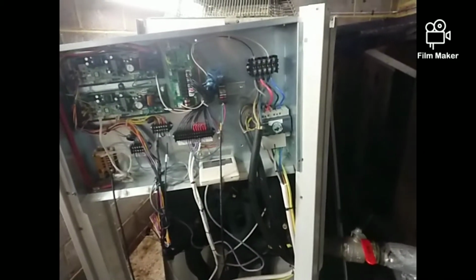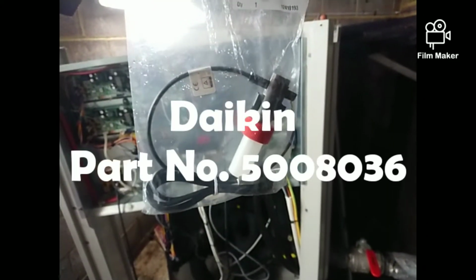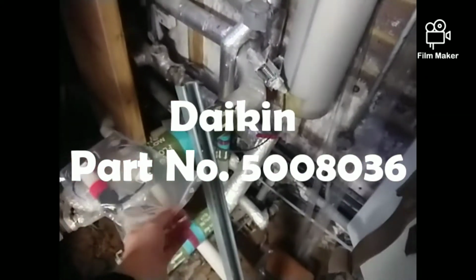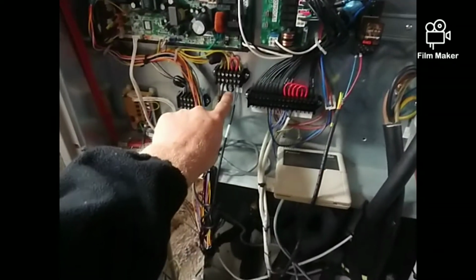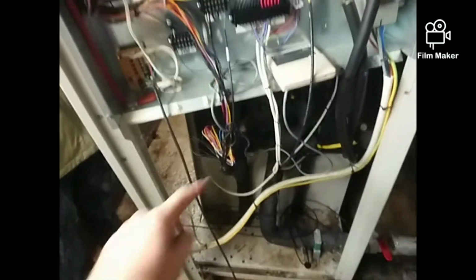So what we've had to do is order one of these, which is a generic part. All the flow switches are the same from Daikin, available I think it was a couple of days turnaround to get that ordered. And then these simply disconnect from X4M, and they're underneath this little lagged bonnet here is your flow switch, and I believe they just unscrew and then screw back in. But on this system, because of the size of it, there's two. So there's one on that side, and there's also one on this side, as you can see. And we figured it out just by pulling the cable back that it was the left hand side which had failed. So now we're going to go through replacing it.